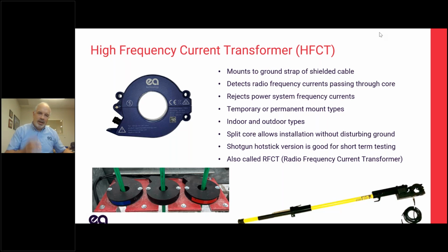If it's a split core, I can clamp it around an existing cable. This picture down the lower left shows environmentally hardened HFCTs that can go outside. If we have outdoor cables, we have outdoor grounds, we can do that. And we're also showing a hot stick, where you can temporarily use the shotgun hot stick to mount an RFCT on a ground strap for spot testing.